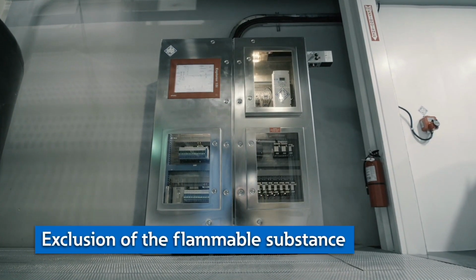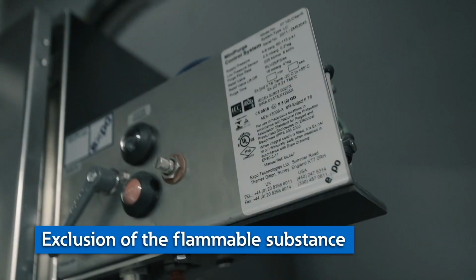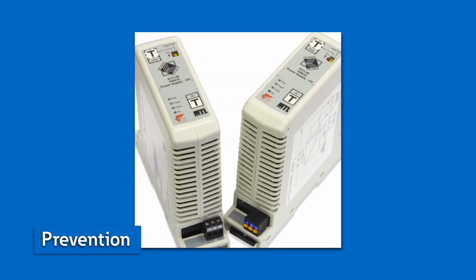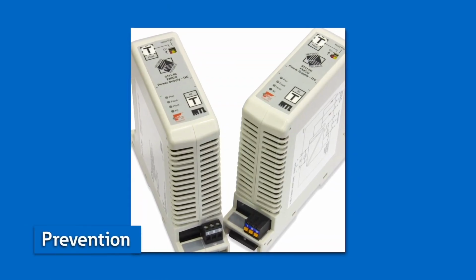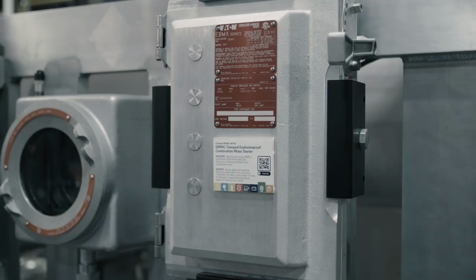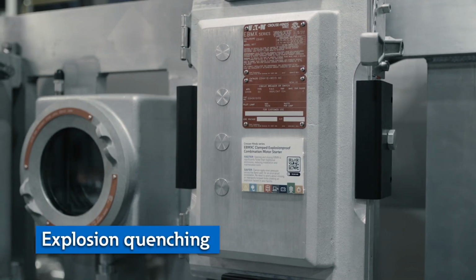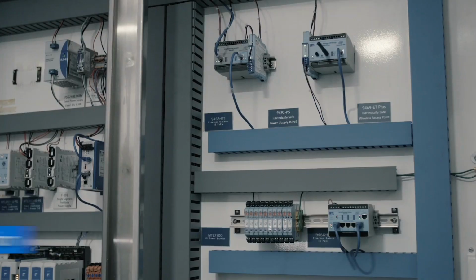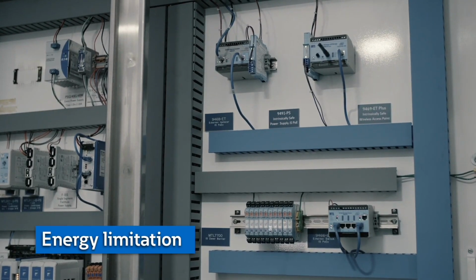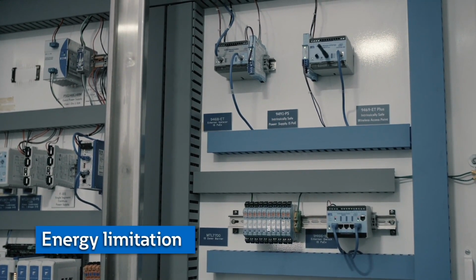There are different physical ways to mitigate an explosion happening with the equipment, and they are exclusion of the flammable substance, like pressurized, sometimes called purging equipment. Prevention of component sparks or hot surfaces, like a non-incendive system. Explosion quenching, like XP, explosion proof. And energy limitation, like what we call intrinsically safe.